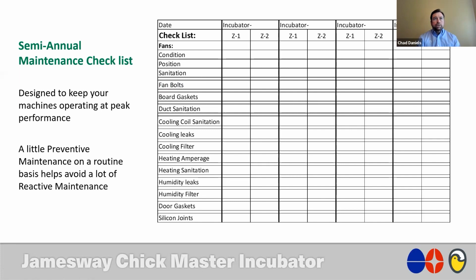Obviously looking at board gaskets, duct sanitation, cooling coil sanitation. And again, with cooling coils, if you have a Millennium machine where you have split cooling, you have basically 4 coils in that machine, 2 in the front, zone 1, and 2 in the rear. And those coils have fins on them, and they do have a tendency to collect a lot of debris on the coil itself. And so it's important to semi-annually check these coils and make sure they don't have a lot of debris buildup on those. And so that becomes important, even if it's a non-Millennium.